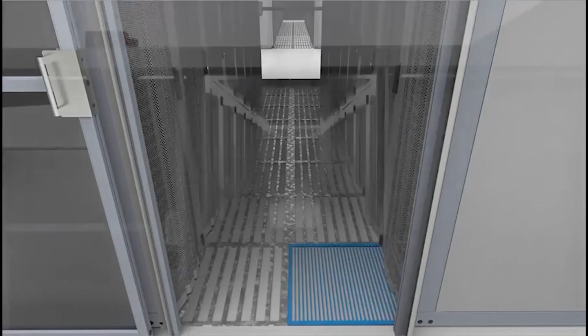Whilst there have been minor bolt-on improvements to address cooling issues, such as aisle containment and HD air vent tiles, these are driven mainly by the need to bring more power to the rack, not for environmental reasons. When these solutions don't work, DC managers are forced to remove or spread racks to increase air volume, wasting valuable real estate just so the cooling technology can keep up.